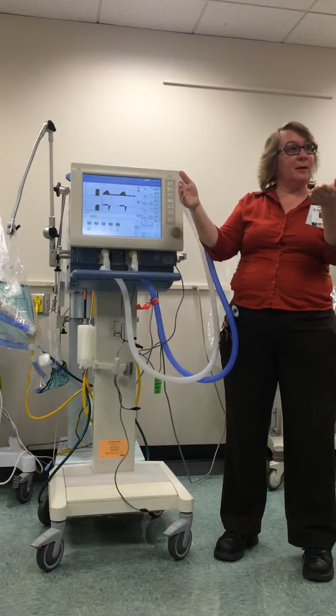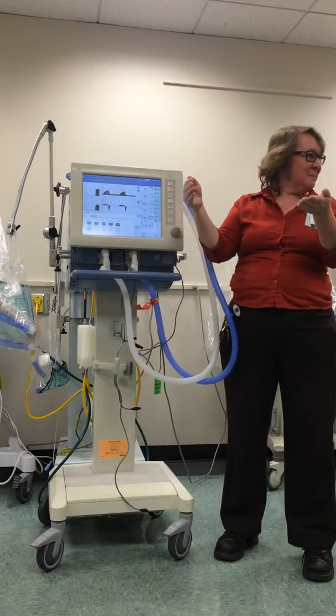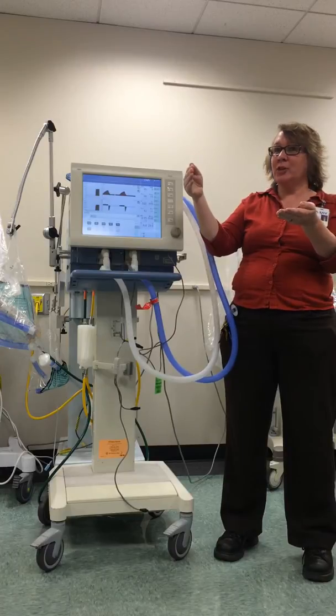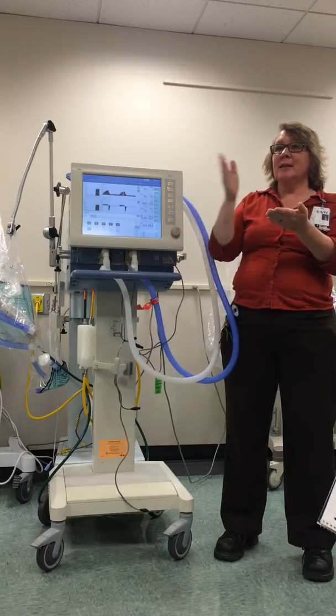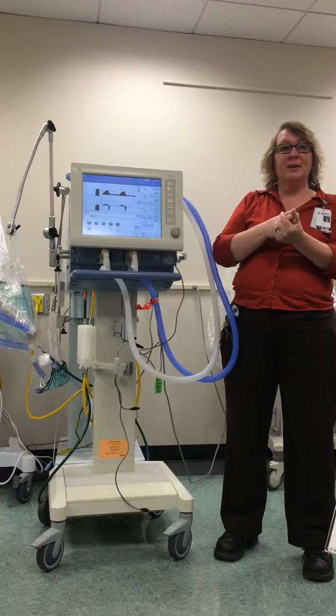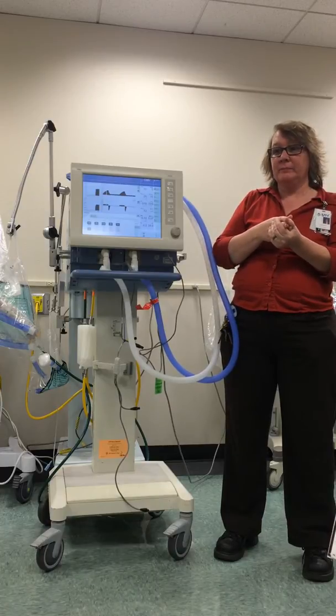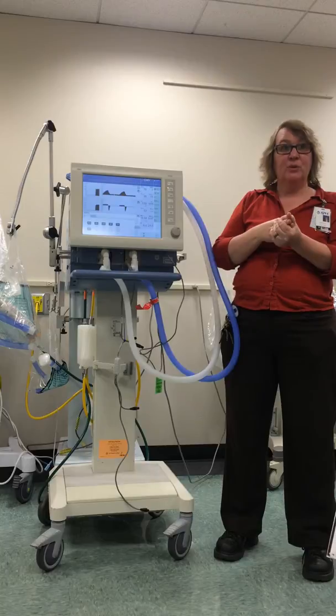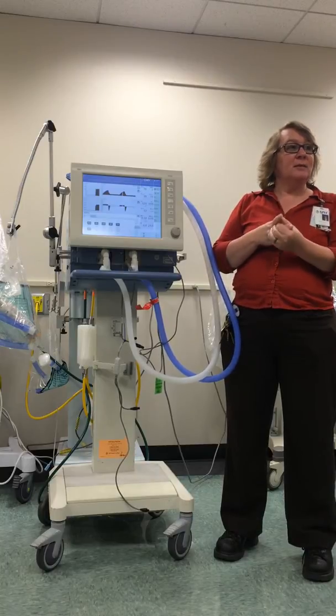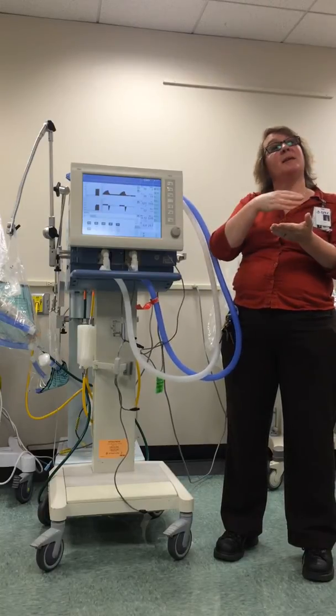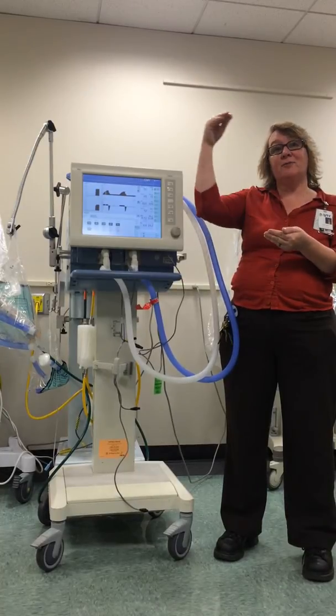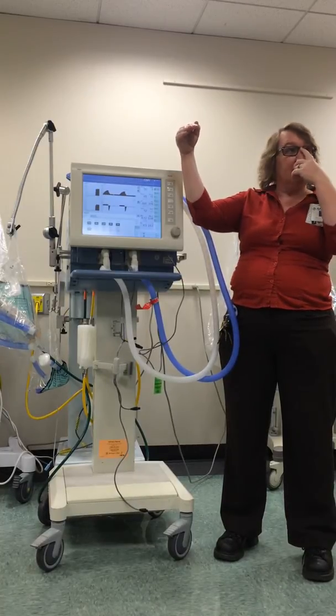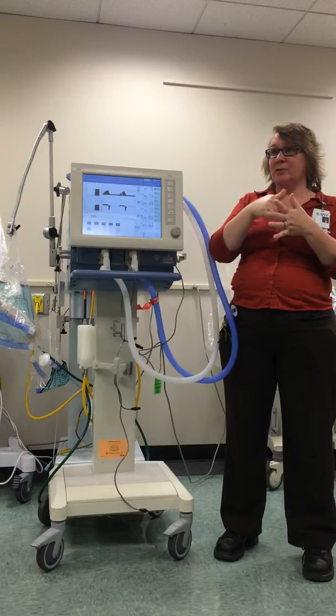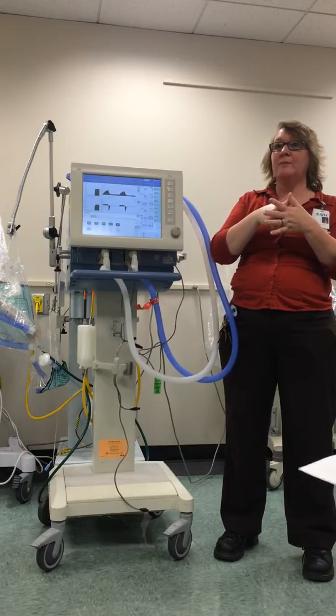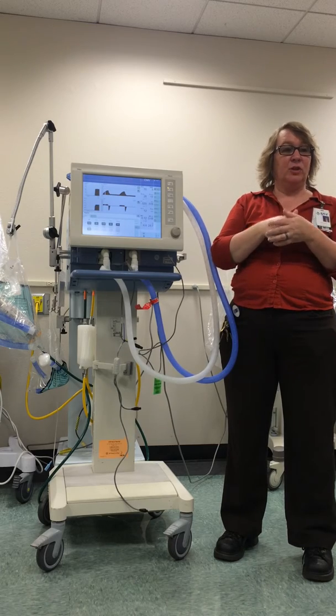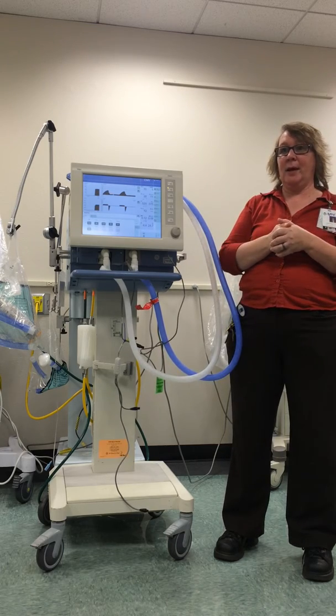Did I do that math right at this time of the day? Yeah. So it's saying alarm when I get to 34. So what you want to do is set your spontaneous frequency on this ventilator. It's very simple, to 10. Now 10 above, which is what you're going to learn for all the other vents. Typically we want to set it 10 above. So if my rate is 12, I would set it for 22, which is 10 above. This ventilator counts only the spontaneous breaths. So you've set it for how many you don't want them to go above the set rate. So it's 10. So you don't add the two together, just make it 10, okay?